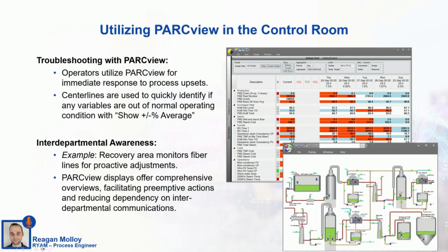Well, they can then go and find a flow tag for their chilled water flow. You can pull the tags for the valve position on that chilled water line, and drop those right onto the trend with your temperature tag, the initial tag they noticed was something wrong with. And they can very quickly see, okay, it looks like this was the problem. This valve started closing off for some reason here right about 4 hours ago, and my temperature started climbing. So it's very easy for them to troubleshoot the issues they notice using PARCview trends.